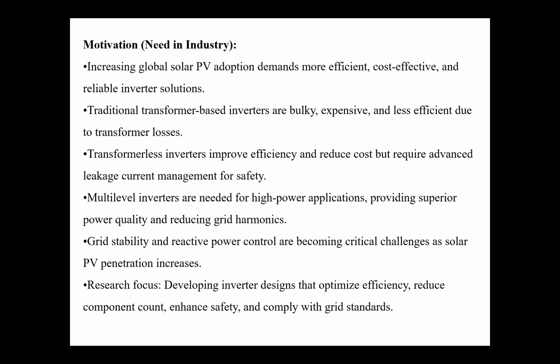Next, what motivated this research: increasing global solar PV adoption demands more efficient, cost-effective, and reliable inverter solutions. Traditional transformer-based inverters are bulky, expensive, and less efficient due to transformer losses. Why is the traditional transformer less efficient? Because it has transformer losses. Transformerless inverters improve efficiency and reduce cost, and require advanced leakage current management for safety. Multi-level inverters are needed for high power applications, providing superior power quality and reducing grid harmonics. Grid stability and reactive power control are becoming critical challenges as PV penetration increases. Research focus: developing inverter designs that optimize efficiency, reduce component count, enhance safety, and comply with grid standards.